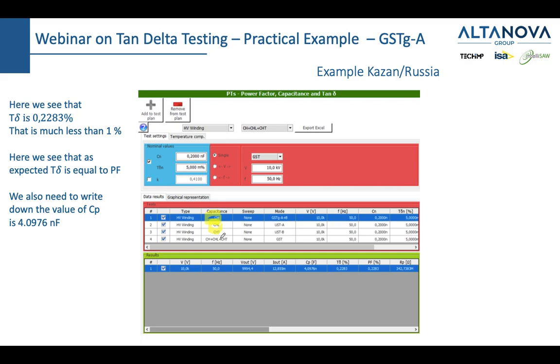You could see that here we have the values for the CHL. I'm sorry, for the CH. So this is the insulation between the high voltage winding and the ground. And you can see here that we wanted to generate 10 kilovolts and 50 hertz. The device actually generated 9,994.4, so this is quite accurate. The total current which was going out, capacitive plus resistive, was about 12.85 milliamps. With our device, you can generate up to 300 milliamps.